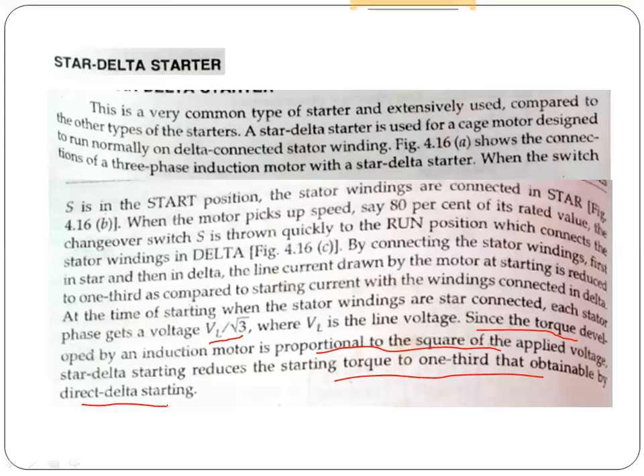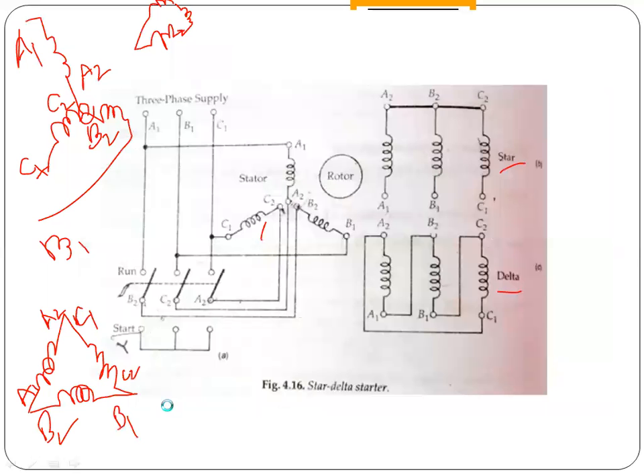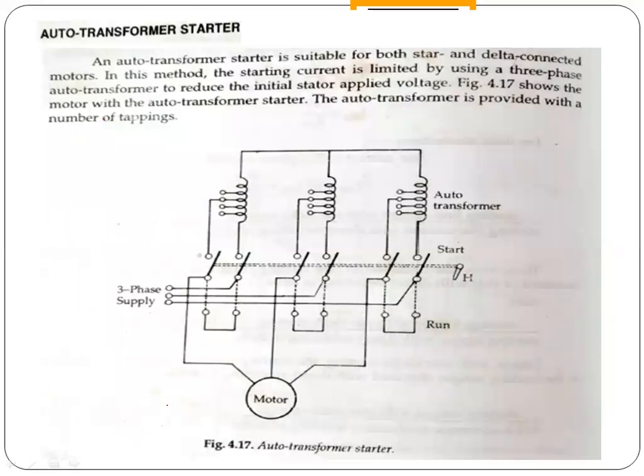Okay, so that is the disadvantage. At the time of starting with star delta connection, the torque will also be reduced to one-third. Now we will come to the auto transformer starter. An auto transformer starter is suitable for both star and delta type connected motors. In this method, the starting current is limited by using a three-phase autotransformer to reduce the initial stator applied voltage.